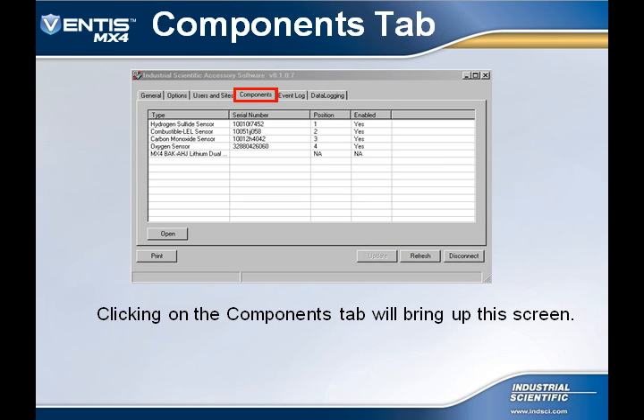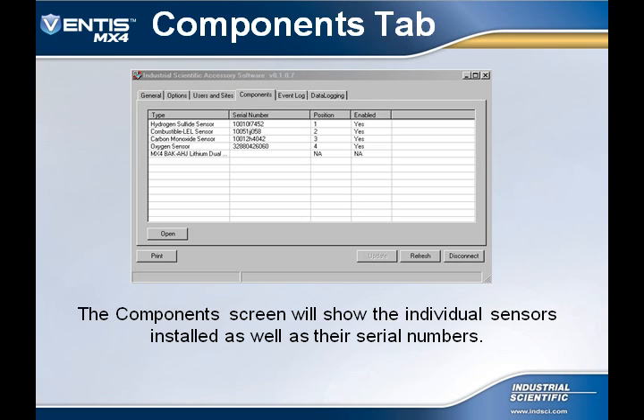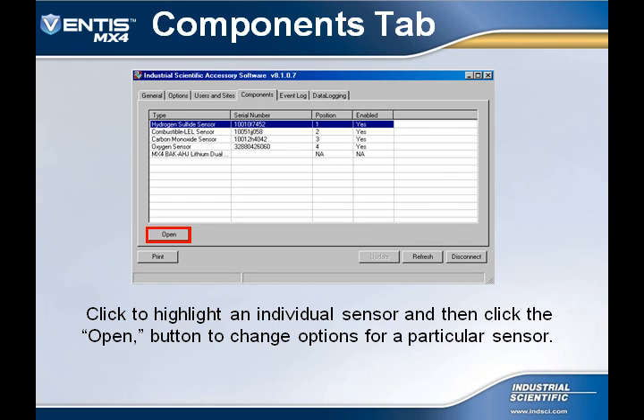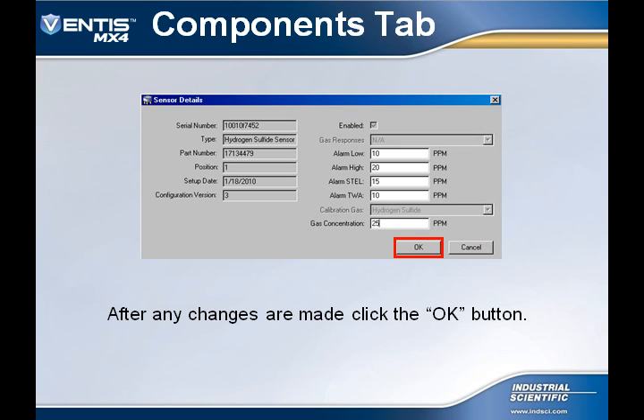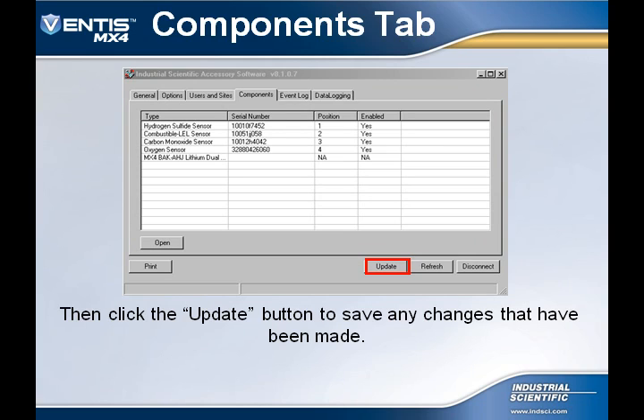Clicking on the Components tab will bring the user to this screen. The Components tab shows the individual sensors installed in the MX-4 and their corresponding serial numbers. Highlight a sensor by clicking on it, then select the Open button to view the individual sensor information. From this screen, the user can change the High, Low, STEL, and TWA alarms for that particular gas. The calibration gas can also be changed. Select the OK button to exit this screen, and if any changes were made, be sure to select the Update button to save those changes.